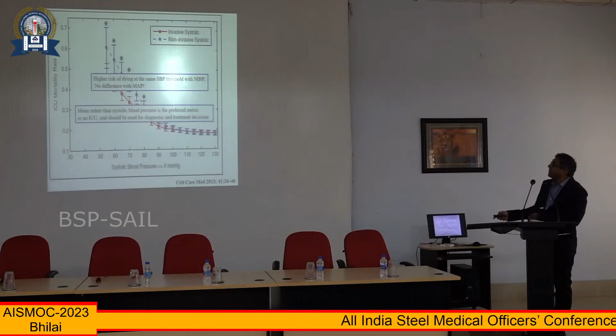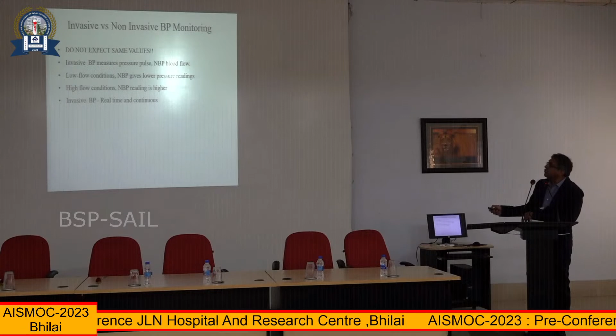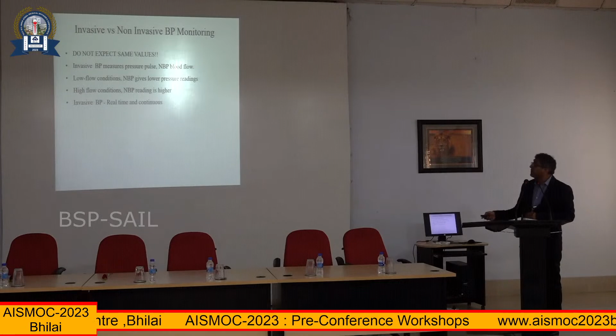So just to highlight the differences, you don't expect the same values, though we always take the mean arterial pressure to be reasonably the same for invasive as well as non-invasive. Then you have other aspects: in low flow conditions it will erroneously show lower readings, in high flow conditions it will erroneously show higher readings, and of course the invasive blood pressure is far better because it will give you real-time monitoring. Okay.